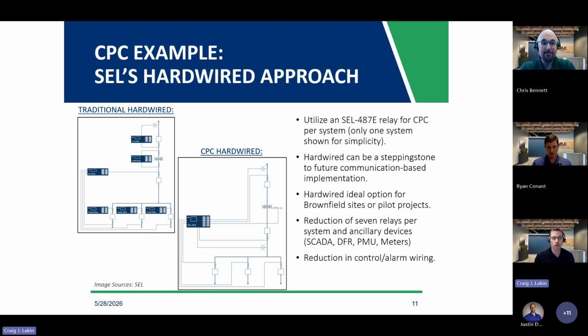To accomplish this, one way is using SEL's SEL-487E relay, and you just use the full capability of the relay. By doing that, you can basically have line, feeder, transformer, bus, and all kinds of different other functions in that same device as needed. So you're not branching out too far from your tried and true methods or the experience of your teams. You're just leveraging the full capabilities of a device you may already be using in the industry. As I mentioned, it's a great stepping stone. So again, if you want to bridge into this space, maybe this is a great example for your first pilot project.